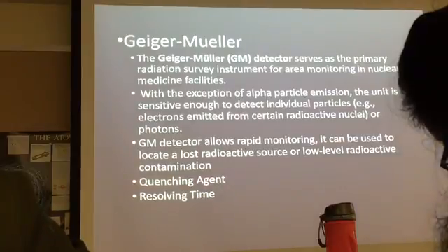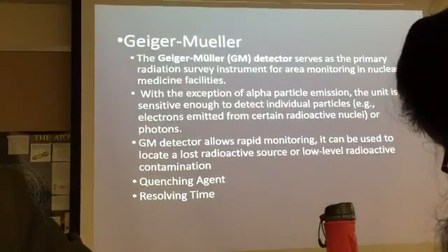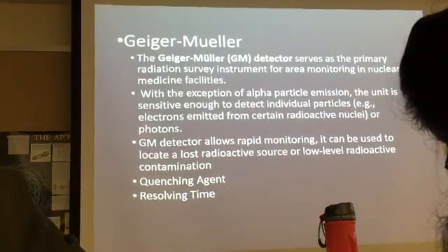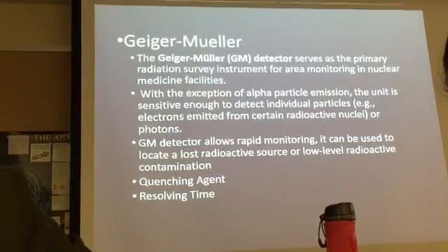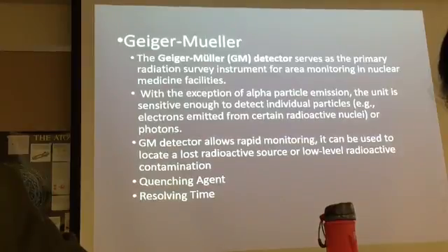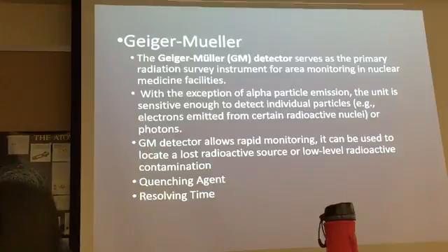The resolving time. The resolving time is the minimum time between ionizations that can be detected. So in between ionizations, you go beep, and then you need a little bit of time to make the next detection. That makes sense? And that's called the resolving time.